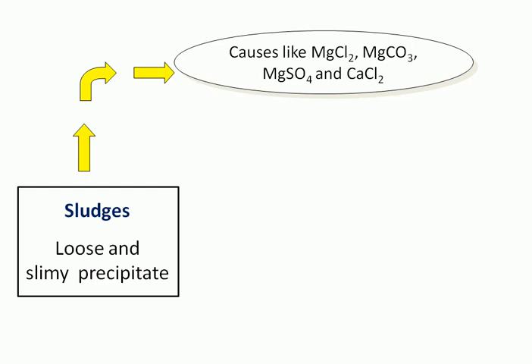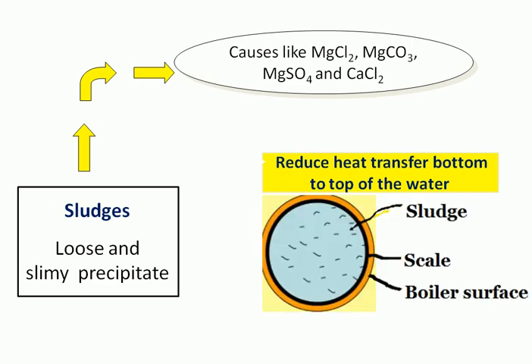Next, sludge. What is sludge? Sludge is a loosely precipitated deposit at the inner walls of the boiler. The causes of sludge formation include magnesium chloride, magnesium carbonate, magnesium sulphate, and calcium chloride — these are the main sources for sludge formation in the boiler. When sludge forms, it reduces heat transfer from the bottom to the top of the water, as the loosely precipitated salt settles at the bottom of the boiler due to gravity.